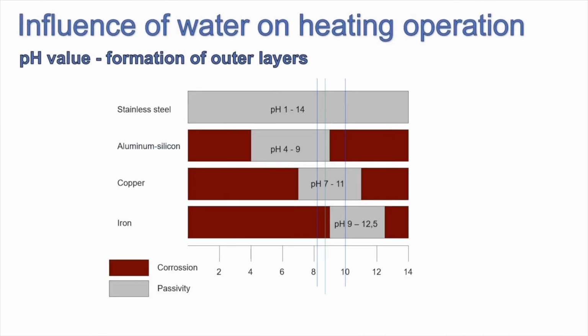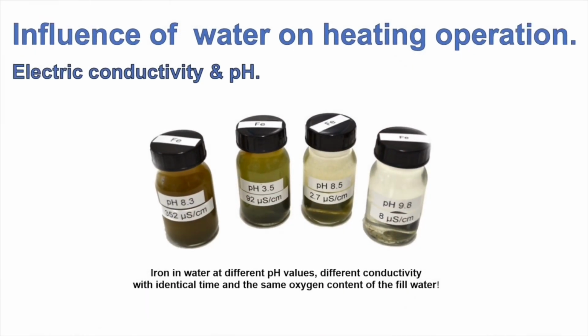Our table here shows the ideal pH range for different metals. As you can see, they're all different. As a rule of thumb, we're looking for about 8.5 because it's good for aluminium and good for all the metals within the system. These little test jars show that you can have the correct pH, but if the conductivity is too high, you will still get corrosion. We really need to be looking at the system as a whole and making sure that all our parameters are correct.